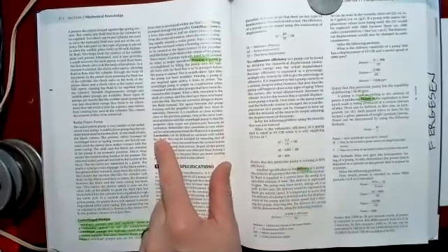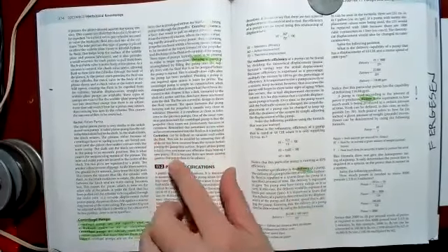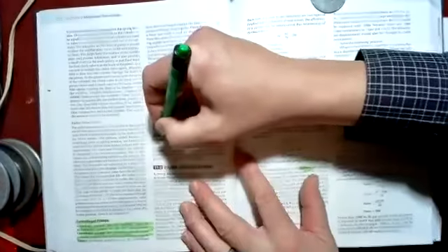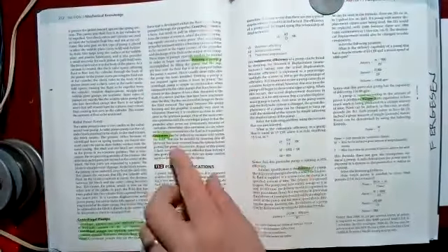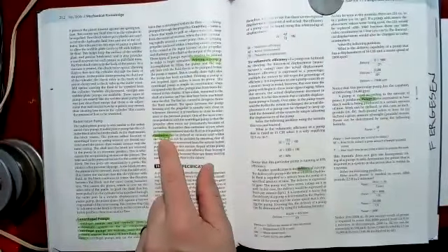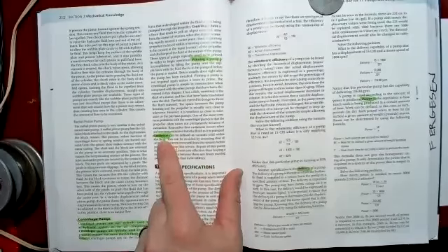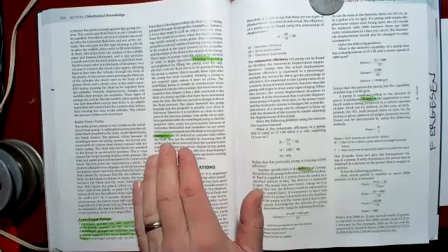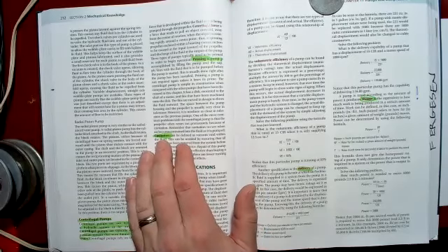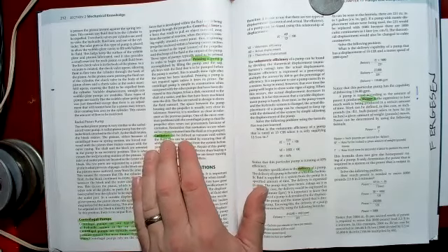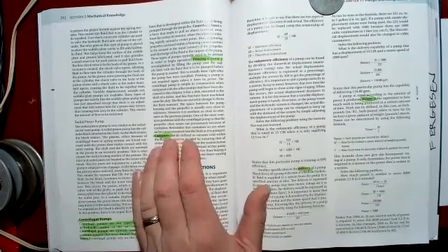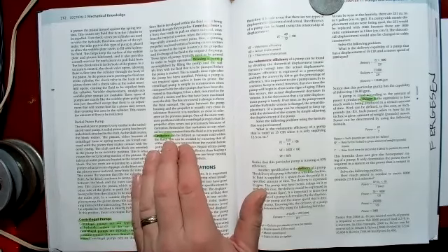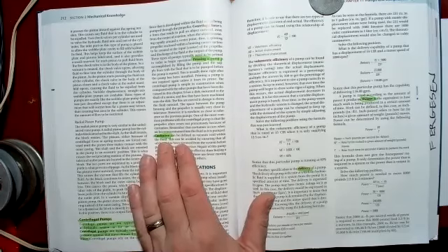Another important concept for centrifugal pumps is the idea of cavitation. Cavitation is a problem. If you hear this thump, thump, thump, thump sound from one of these, it means that you're creating vacuum in the pump impeller, right inside the pump housing itself, right against the impeller. These are like tiny little explosions right on the surface of the impeller.